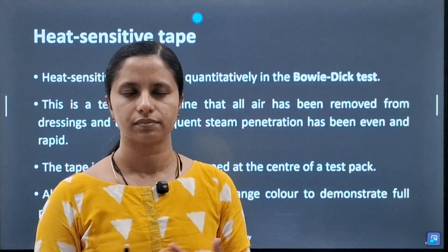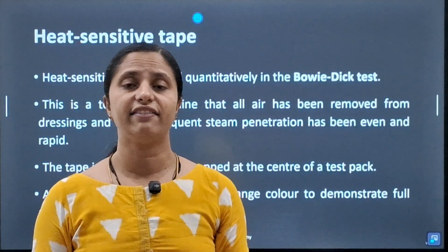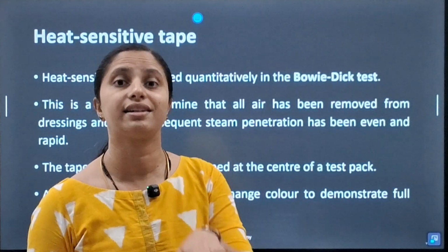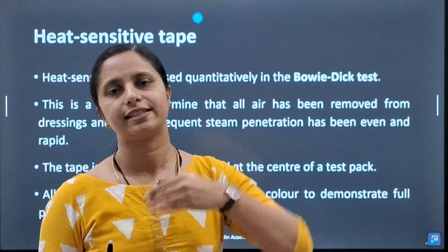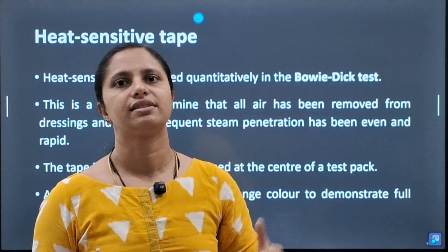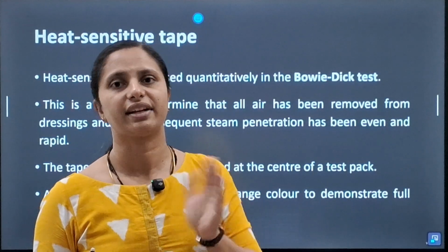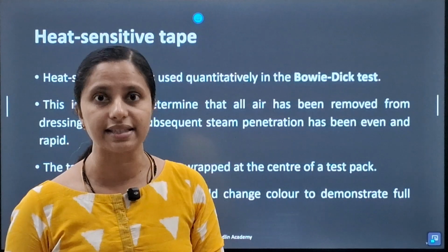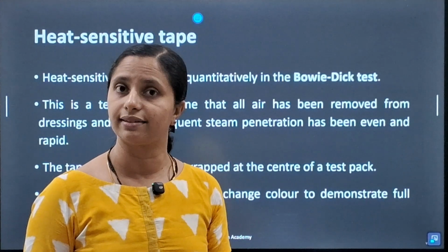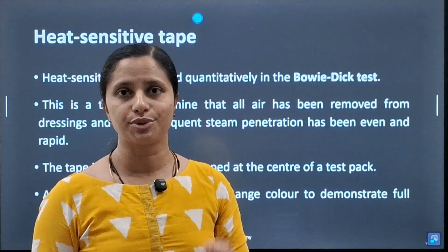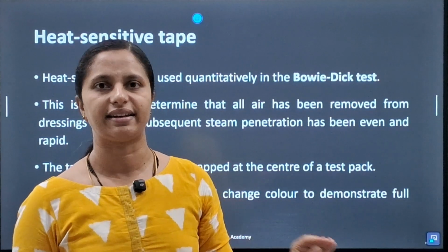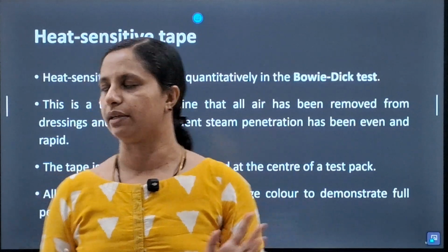If steam penetration is even and rapid, the heat sensitive tape put at the center of the pack for sterilization will be seen with all its stripes turned into a different color. So remember, heat sensitive tape is used in the Bowie-Dick test, and the Bowie-Dick test is used to check whether the steam penetration is even and rapid throughout the sample.